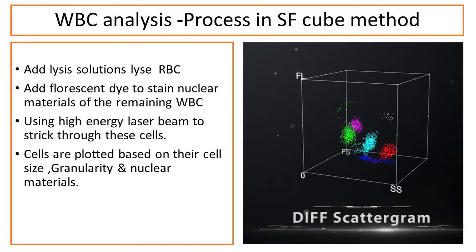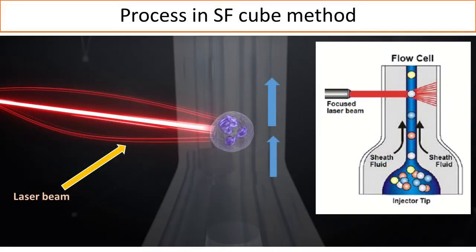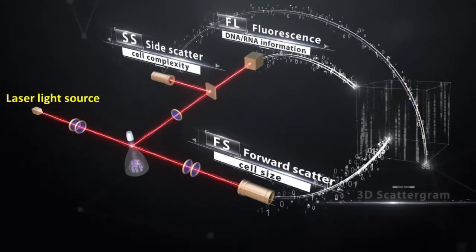In white blood cell analysis, a lysis solution is added to lyse RBCs, leaving remaining WBCs. A fluorescent dye is then added to stain the nuclear materials of the WBC. Cells are injected into a flow cell located in the optical path of a high-energy laser beam, which passes through the cells to measure cell size, granularity, and DNA or RNA materials via forward scatter, side scatter, and fluorescent signals respectively.